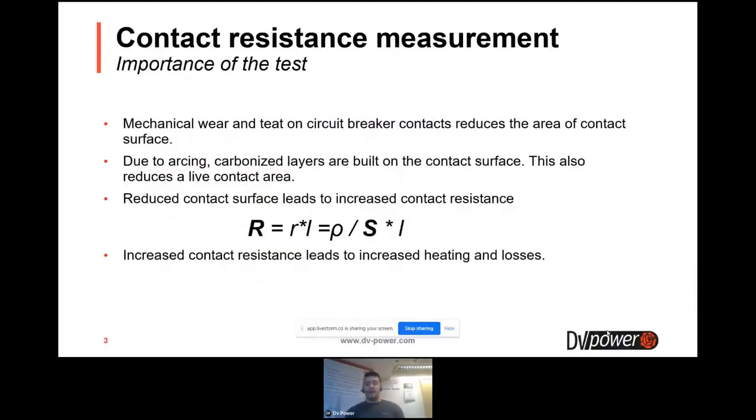So basically, why is this test so important? You know that circuit breakers, medium and high voltage circuit breakers, are devices and apparatus which conduct a very high current, and they should protect other apparatus in the system by breaking the fault current. And during this process, there is mechanical wear and tear on the circuit breaker contacts, and the contact surface can be damaged.